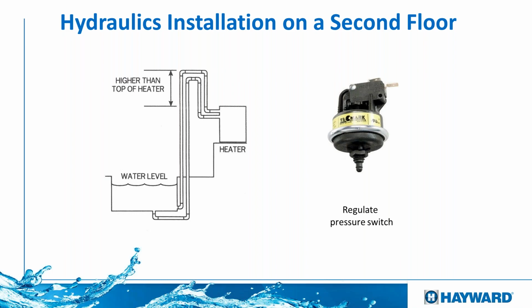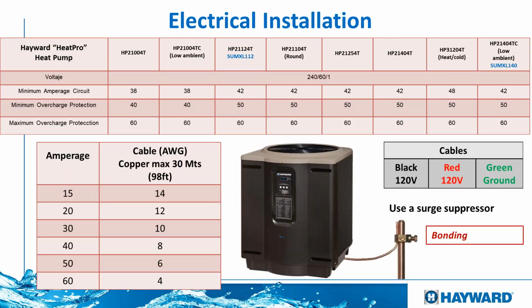For any reason, if we adjust it to the maximum, which is 10 psi, and it still closes because of the weight of the water of that big pool on the second floor, then we'll probably have to install an external water pressure switch that works only with flow, not exactly with weight or pressure. And then we just install that on the low voltage line. We just interrupt the line. Okay, so keep that in mind. And let's continue with this.